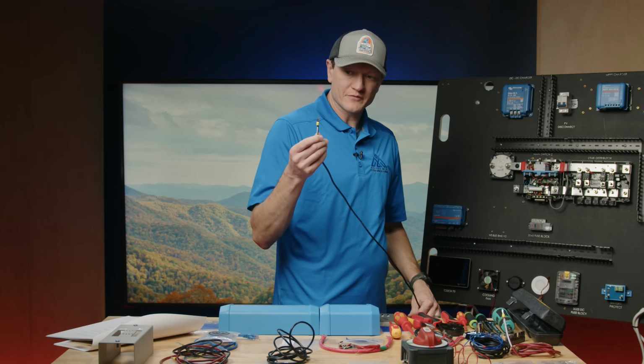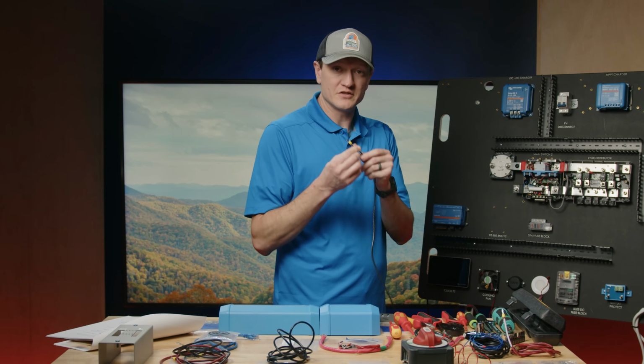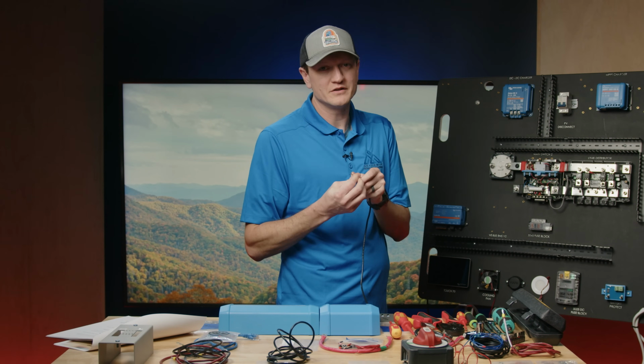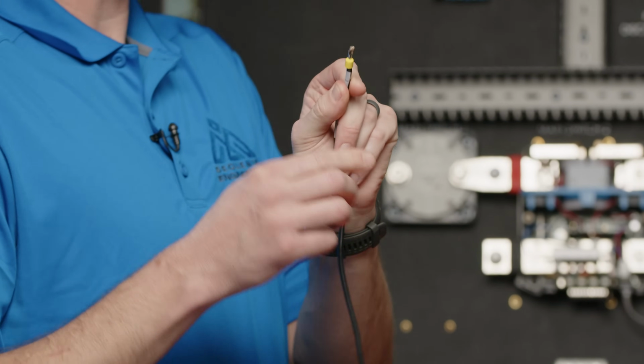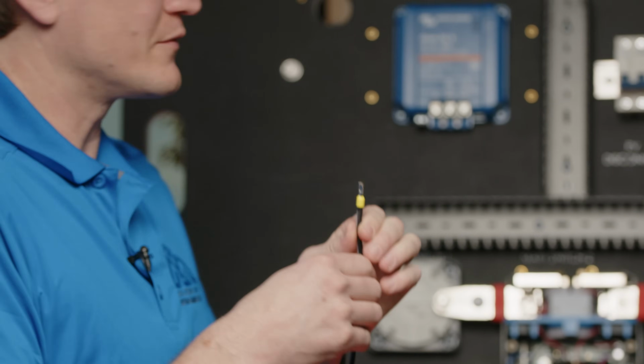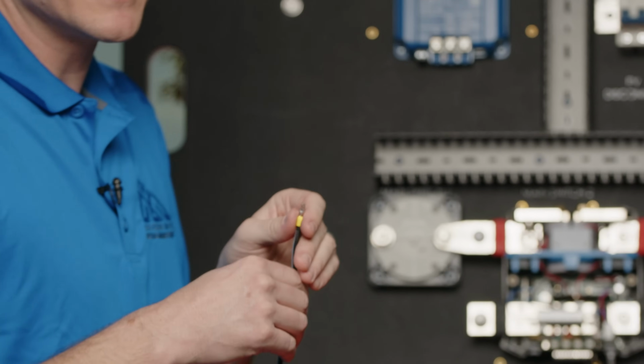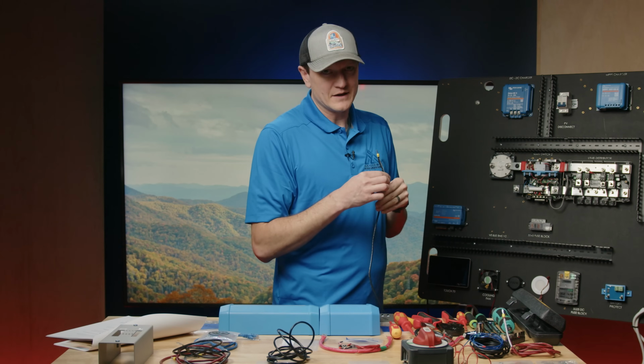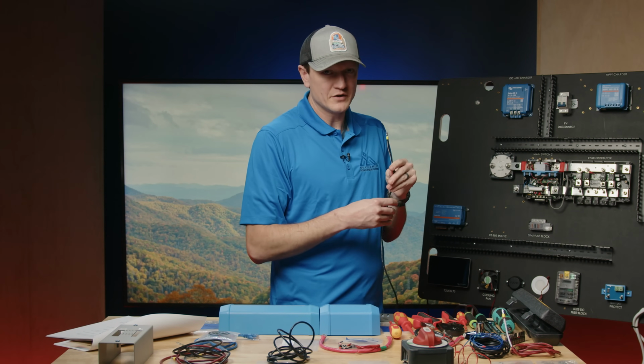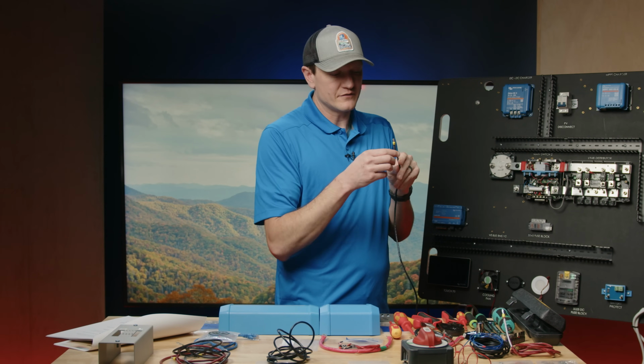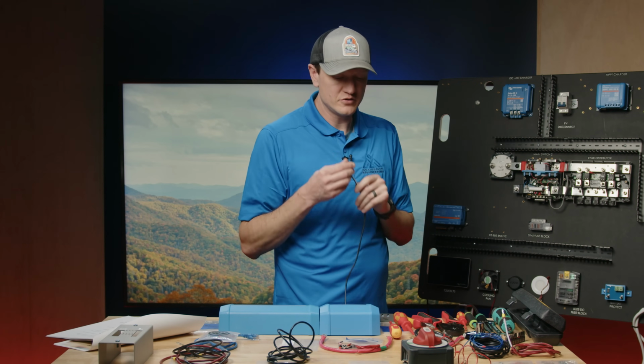We get a lot of questions from customers about whether it's necessary to use a ferrule, and the answer is absolutely. This ferrule prevents stray wires from contacting some other component in the system and causing a fault. I've seen many systems fault because of a lack of ferrules. So yes, do use ferrules.